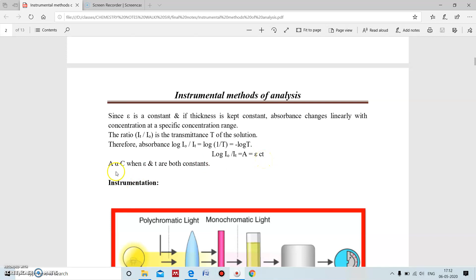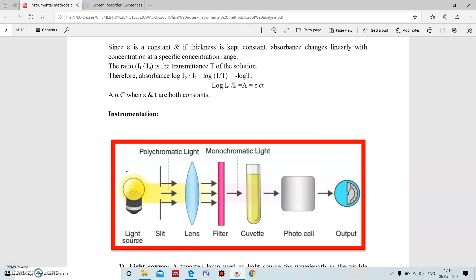The instrumentation of colorimetry involves several parts. It involves the light source, slits, lens, filters, cuvette, photocell and output. The light source commonly used in colorimetry is a tungsten filament lamp. To select a particular wavelength, filters or monochromators are used to split the light from the light source. A sample holder, a test tube or cuvette, is used to hold the colored solution. They are made of glass for visible wavelengths.